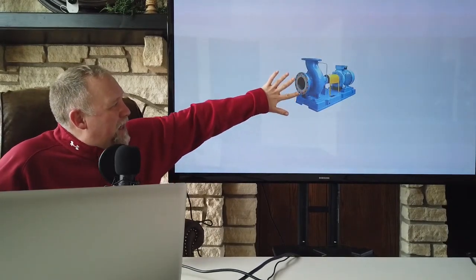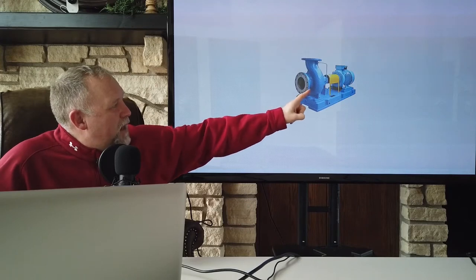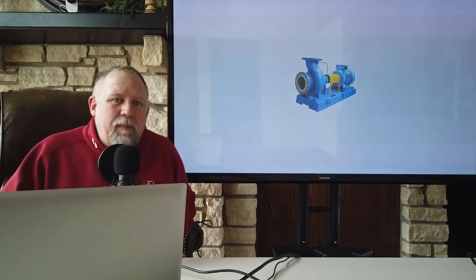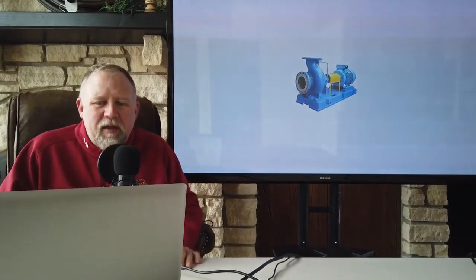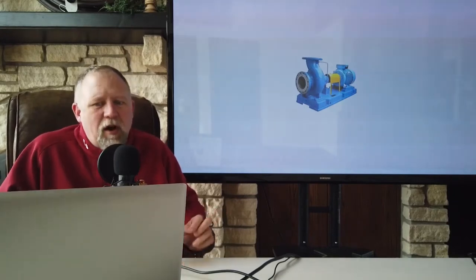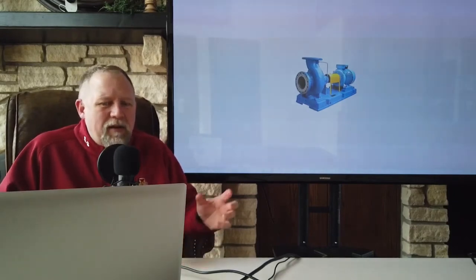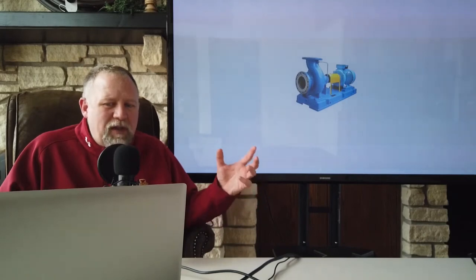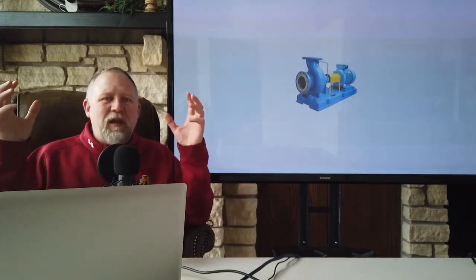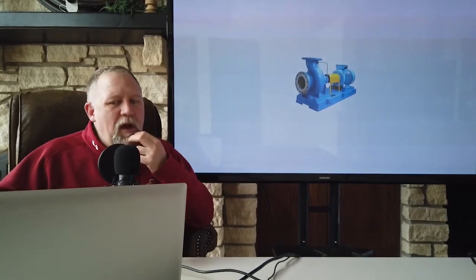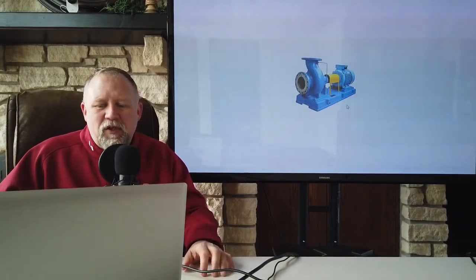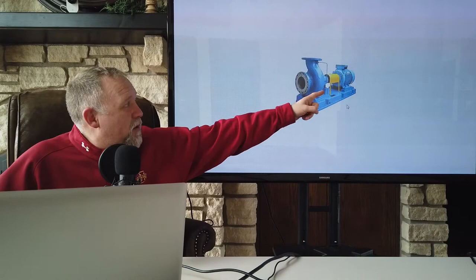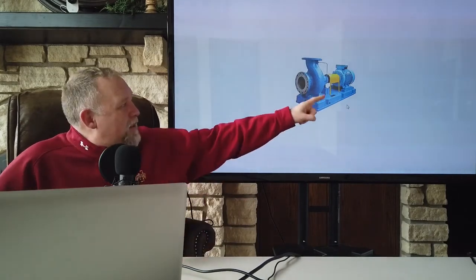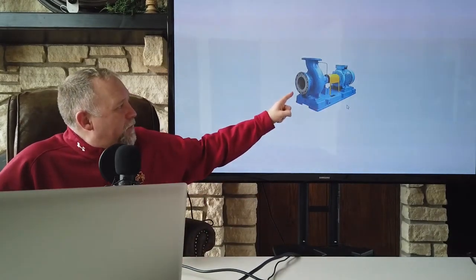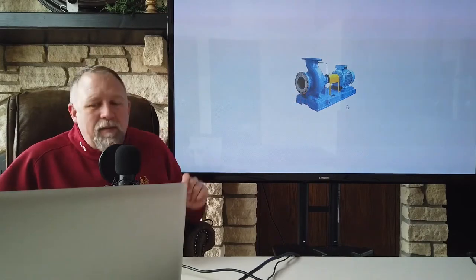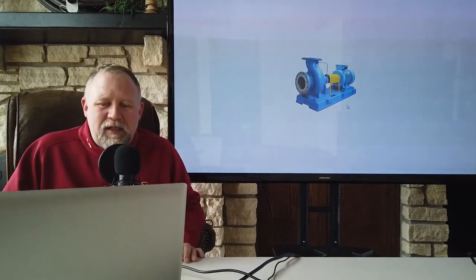Now, this is the mechanical part on the left side. The yellow item in that picture is the coupling. That's actually a guard for the coupling. That is where the shaft that goes to the impeller connects to the shaft that goes to the motor. On the far right part of this picture, the back side, that's the motor side. So we connect the motor to the impeller, and the part in the middle, the coupling, connects the two.